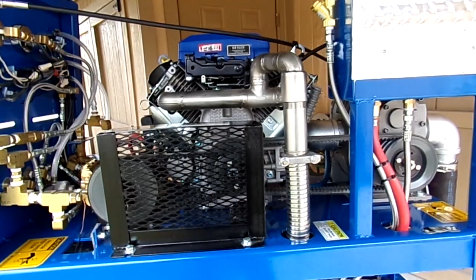This will do 2,000 plus PSI working pressure. Why turn down a pressure job these days? You want all the jobs. You don't want to be subject to saying, well, I can't get over 1,200 because I've got some other system manufacturer that can only do 1,200 PSI. A lot of these manufacturers purposely eliminate the high end because they have cheap copper core heat exchangers that blow up over 1,200.